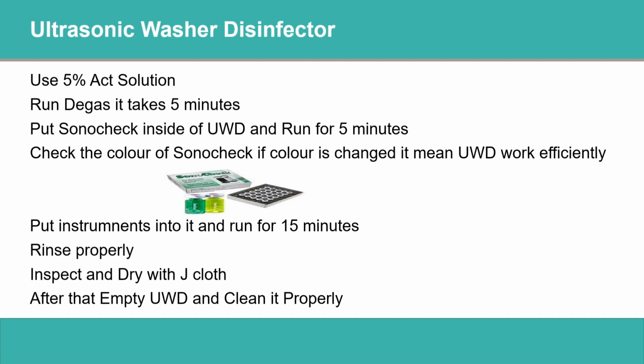After the color is changed, it means it is validated. So once the color has changed, we put the instrument into it and run it for 15 minutes. After 15 minutes, we rinse properly, inspect, dry, and after that we put it in the automated washer disinfector. After the automated washer disinfector, we inspect and check that it is functional, accurate, and neat and clean or not. If it is functional, accurate, and neat and clean, the CSSD technician keeps the instrument inside the window.